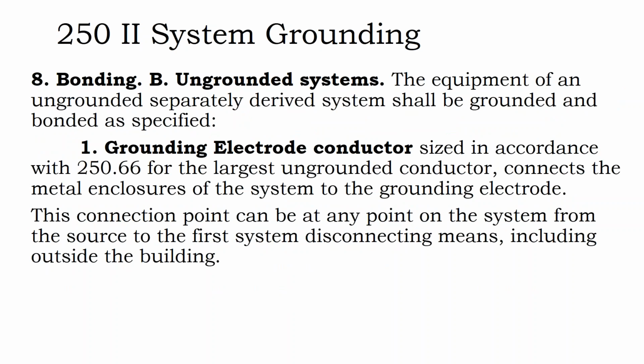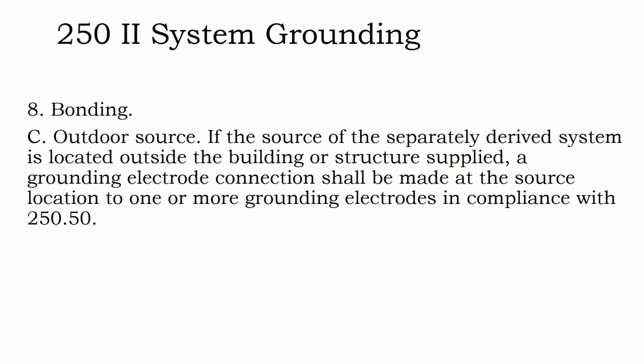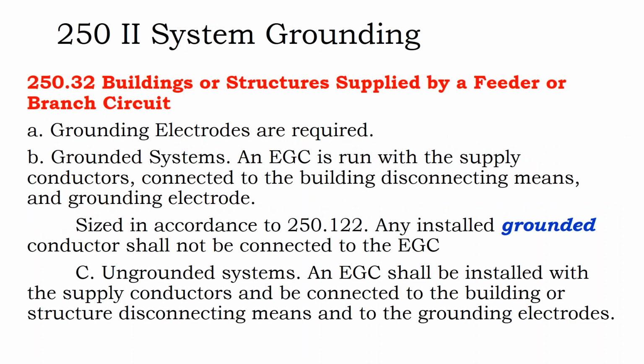Then Table 250.66 is used for sizing that. We're not at that point yet, so we're getting there. Generally, you're sharing the grounding electrode. So if you have a ground rod already on your building, you're using that as your grounding electrode. Although in solar design, you run 2 ground rods, so if you only have one, that's a good opportunity to put in another. It's much easier to drive your ground rods when you have mechanical equipment on site, like a forklift or something like that, where you can use equipment to drive the ground rod into the ground rather than a sledgehammer.